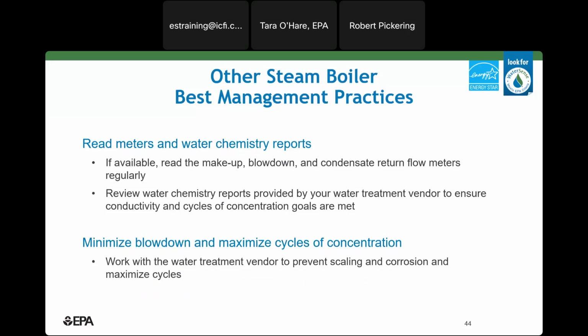So some concepts presented earlier for cooling towers also apply to steam boilers. You'll want to install and read makeup and blowdown meters. You want to maximize your cycles of concentration by capturing as much steam condensate as possible and by minimizing blowdown. And then again, work with a qualified water treatment vendor that is specialized in water efficiency to help you maximize your cycles while still preventing scaling or corrosion within your boiler system. By working with someone who knows what they're doing, this should reduce the amount of water use, your chemical use, and your overall costs.